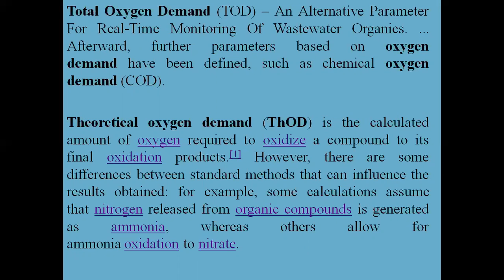Total Oxygen Demand and alternative parameters for real-time monitoring of wastewater organics: further parameters based on oxygen demand have been defined, such as Chemical Oxygen Demand (COD). Theoretical Oxygen Demand (ThOD) is the calculated amount of oxygen required to oxidize a compound to its final oxidation products. There are some differences between standard calculation methods; for example, some assume the nitrogen released from organic compounds is generated as ammonia, whereas others allow for ammonia oxidation to nitrate.